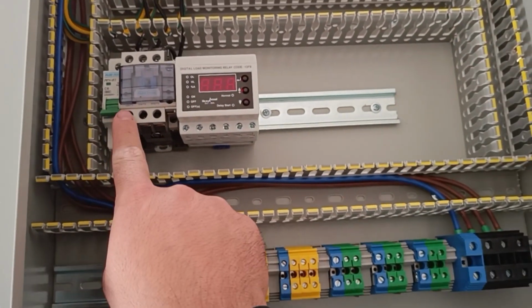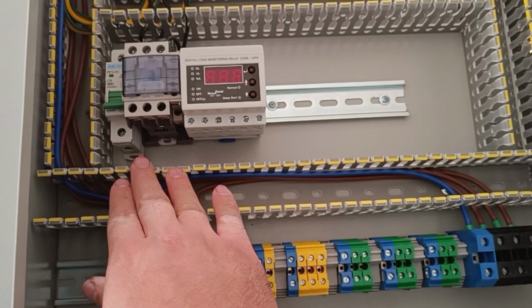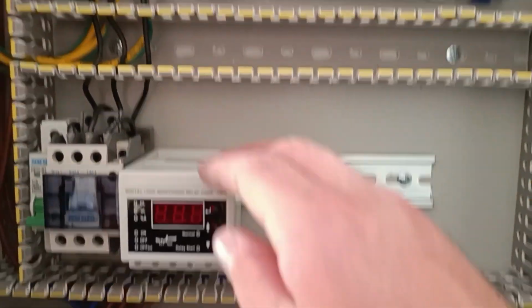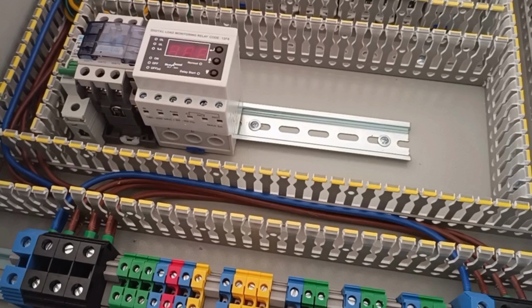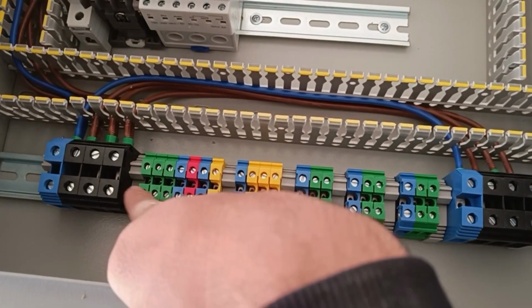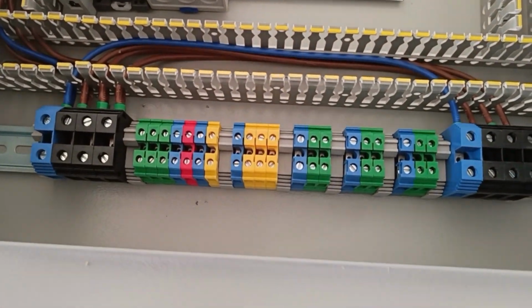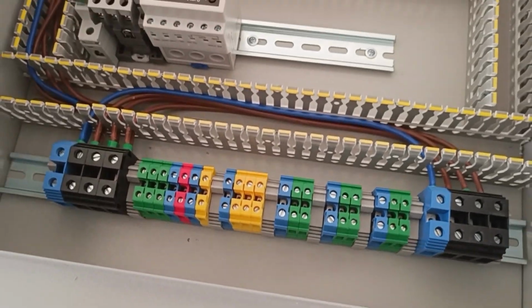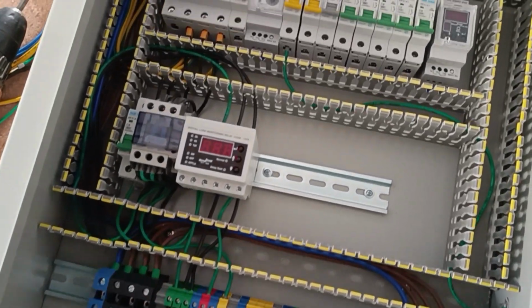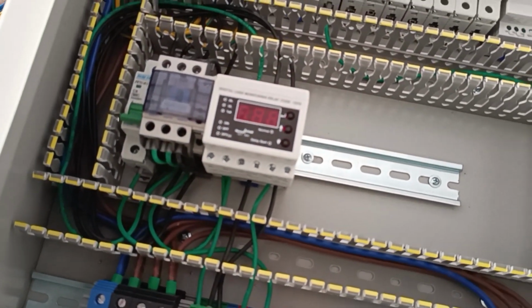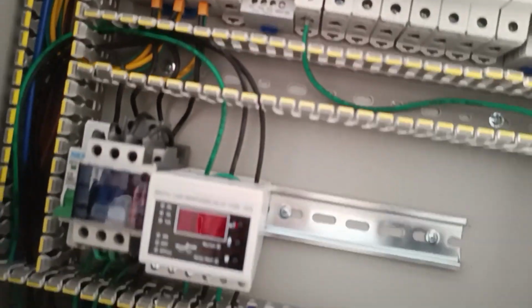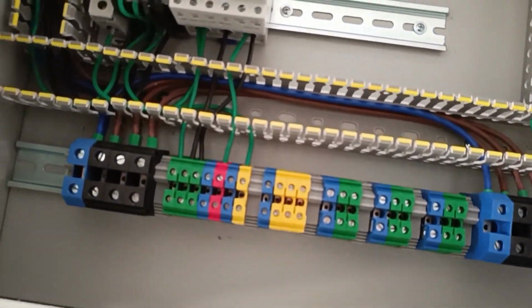Now we connect three phases from the output of the contactor to the output terminals. However, before that, we pass the three-phase wire through the current controlling relay so that the output current of the three phases can be calculated and displayed, allowing the circuit to be disconnected if necessary. This work is done. Please pay attention to the wiring.